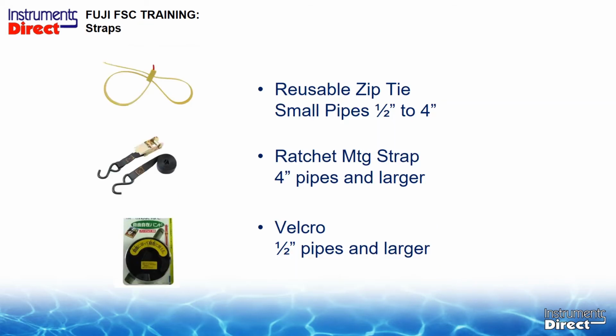If you need to put the meter on the pipe, of course, we need to use some straps. The old days used to use flexible straps, and now here's the current type of technology we use. Small pipe transducers, we use the reusable zip tie, which are very handy. Medium size, we use a ratchet strap, and then for the old timers, we still have the good old Velcro straps, which you can wrap anything to a pipe with. So whatever your preference is, it's easy to put on the pipe, or as we said, this type of transducer, you can hand hold it.